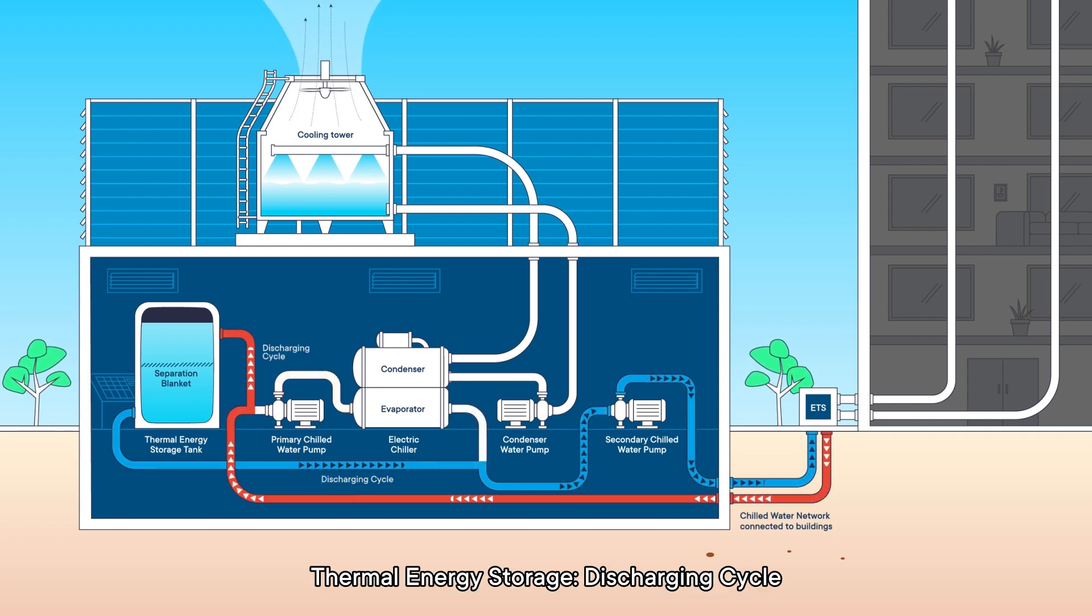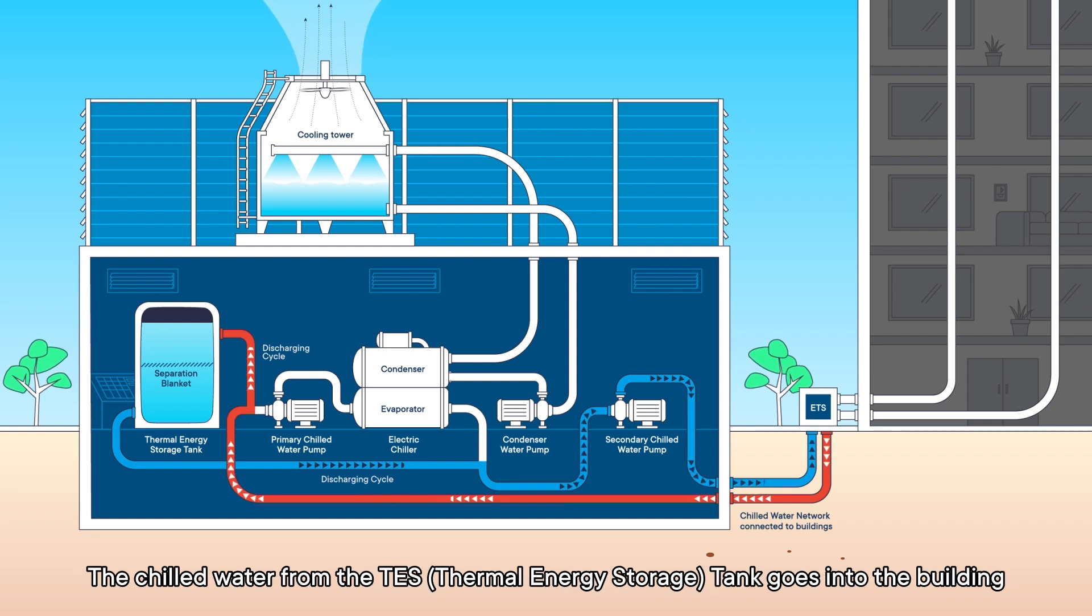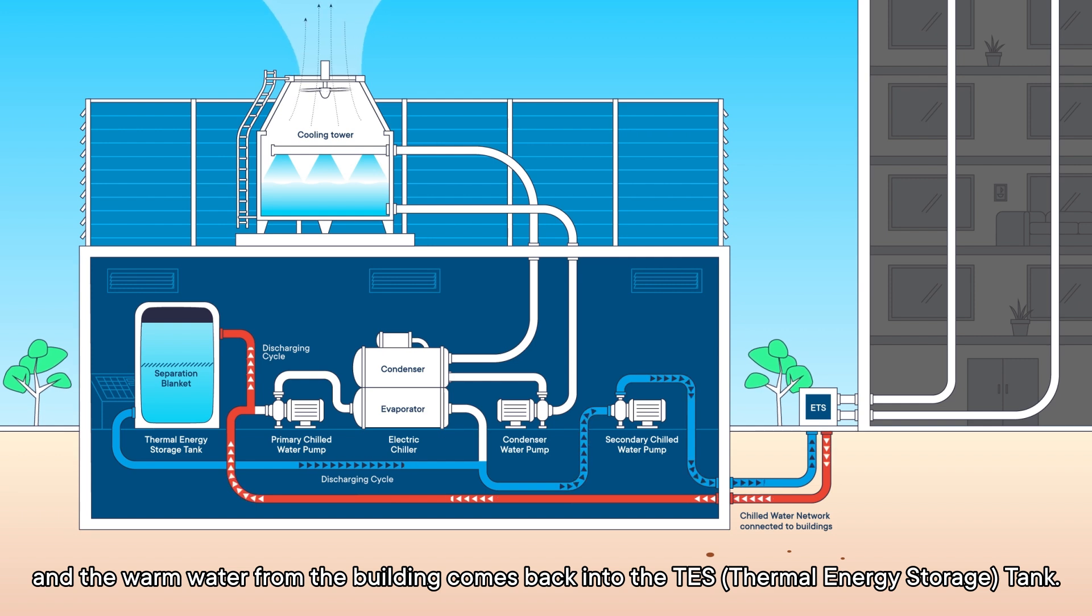Thermal energy storage discharging cycle: This happens during the day when there are peak surcharges on the electricity tariffs. The chilled water from the TES tank goes into the building and the warm water from the building comes back into the TES tank.